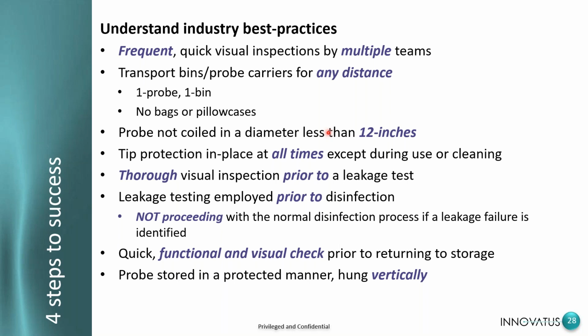Tip protection in place at all times. This is something I constantly see where people are not doing something so simple, but yet so effective, which is using a tip protector. A tip protector should be used at all times, unless you're using the probe on a patient or you're cleaning the probe. Other than that, there are no exceptions. Even when you're storing the probe in a cabinet, those probes get moved around. When people remove them from the holder within a cabinet, that tip may bounce around, and as sensitive as the arrays are on TE probes, the smallest impact can damage the array. And so we do want to see a tip protector on the probe at all times.